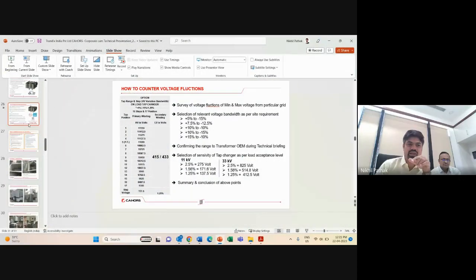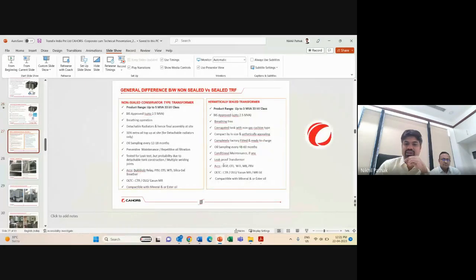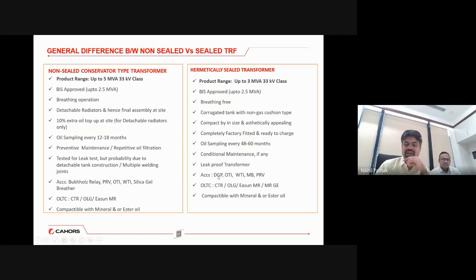so I think my screen is still shared, no? Yes, yes. So here you will find the detection of gas and pressure. This is always there. Detection of gas and pressure gives support for slow developing faults, which are sensed by the Buchholz relay, and the pressure relief valve, which is a part of the pressure gauge. This integrated device will take care of electrical tripping of the transformer and isolate it from the supply, and the manual gauge will open up and discharge the oil in case of any abnormality and short circuit conditions in the transformer. So in both cases, extreme accidents will be prevented, the oil will be released and the pressure will be relieved.